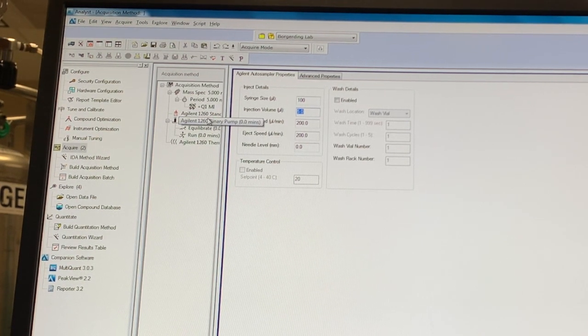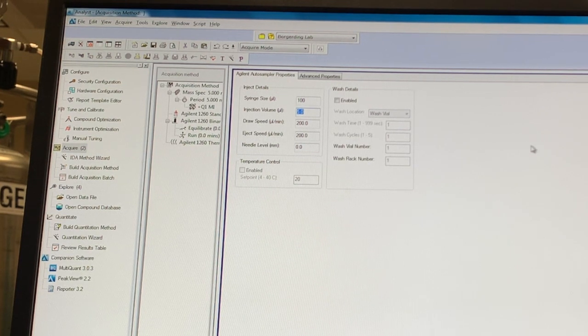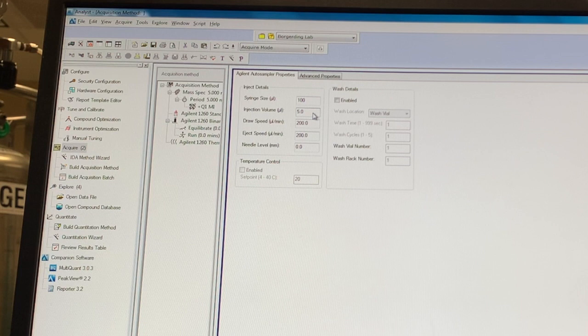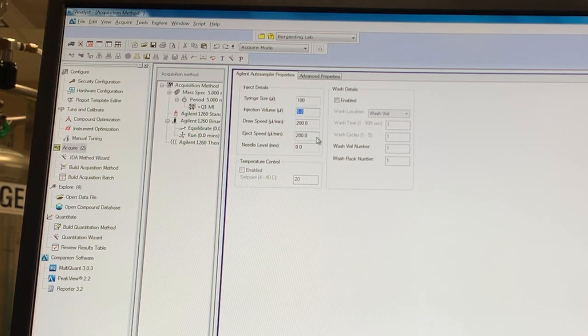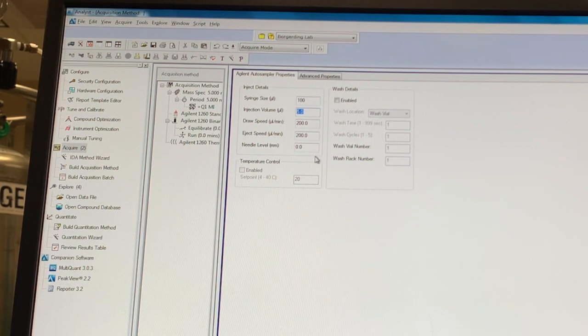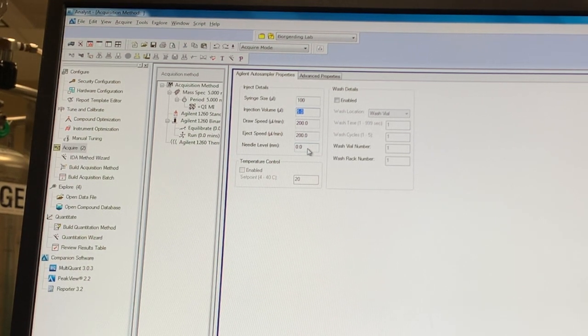The next step in setting up your very first LC-MS method is to determine the auto sampler settings. The auto sampler is the needle that injects into each vial and will draw out a predetermined volume at a certain speed. So here I have the injection volume set at 5 microliters. So my injection needle is going to pick up 5 microliters in my sample and then inject that onto my HPLC column. There are also some other various parameters here. Needle level is how high off the bottom of your vial are you picking up your sample. So if you see any of your sample maybe crashing out of solution, you might want to raise that needle up just so it doesn't suck up any solids. That would be bad for the instrument.